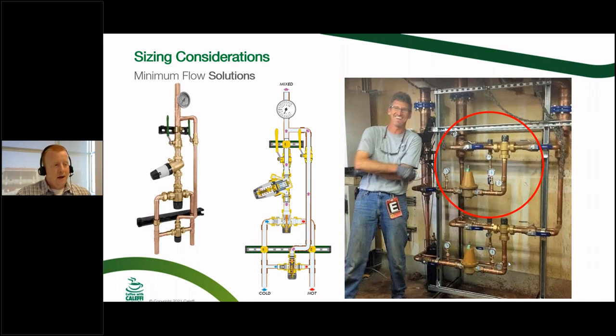In a lot of cases, they'll open up a number of fixtures to make sure that the valve works under the worst case scenario. They want to turn on all those faucets, but that's not their demise. Their demise is going to be when that one single lav turns on, and all of a sudden it's 80 degrees, then it's 140 degrees, and it's just bouncing all over the place. So you need to make sure that you're meeting those minimum flows, and one way to get around that is with that high-low assembly.